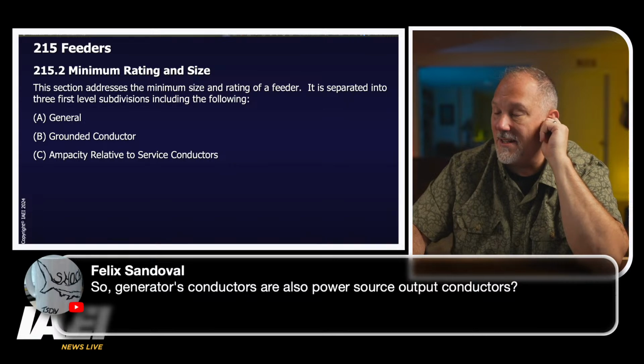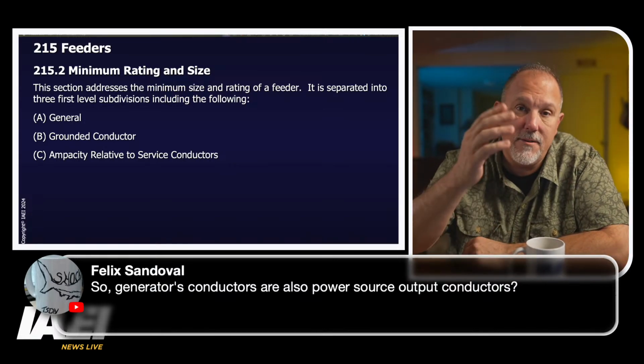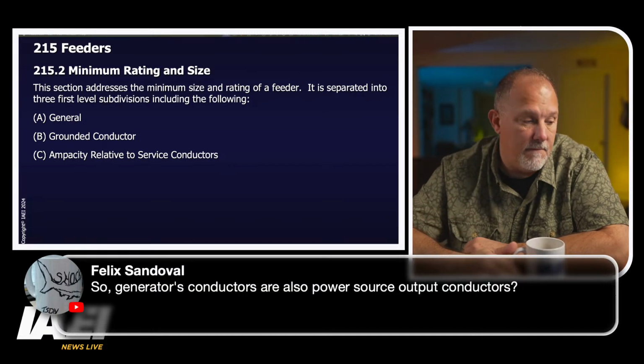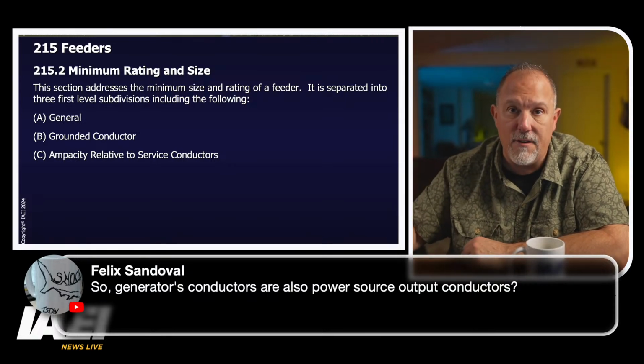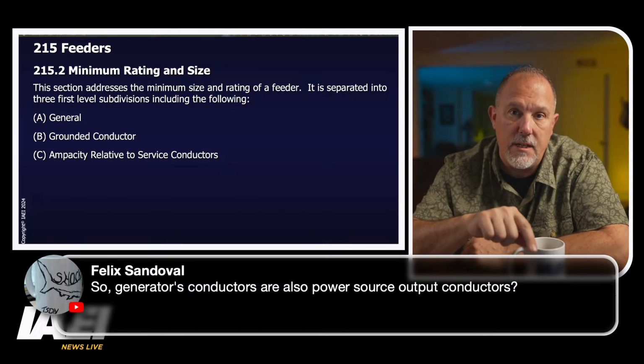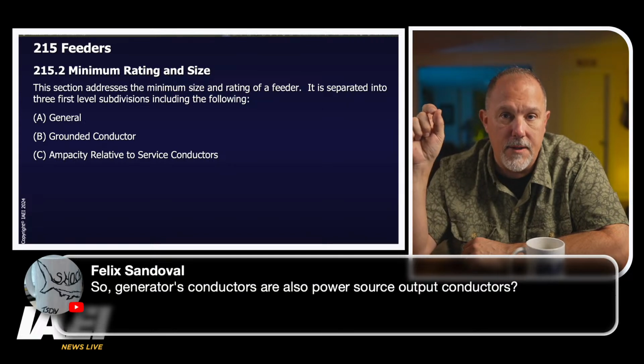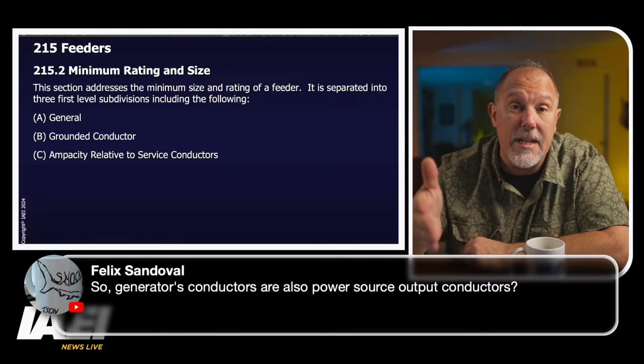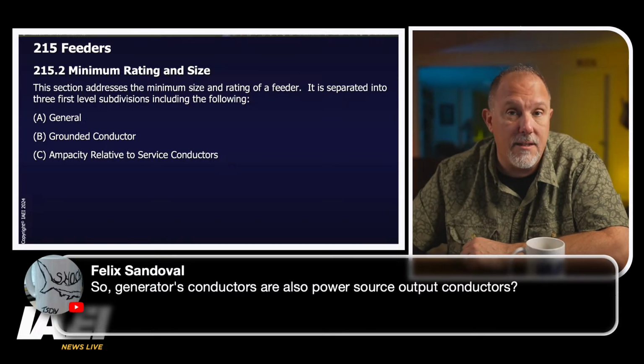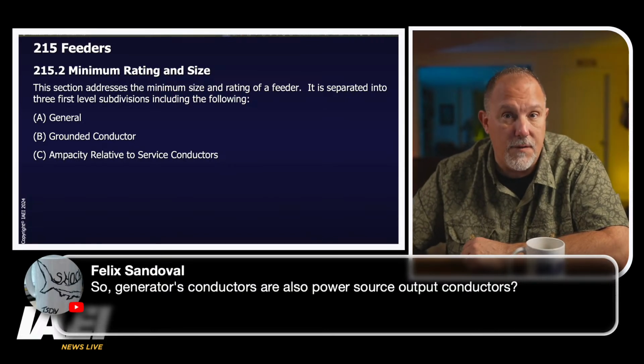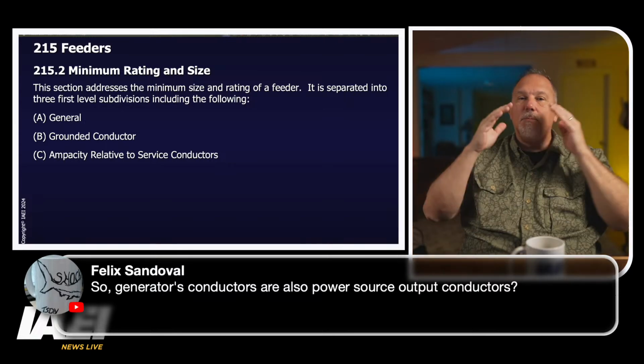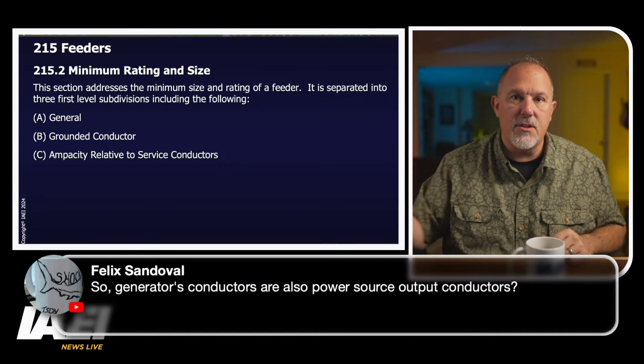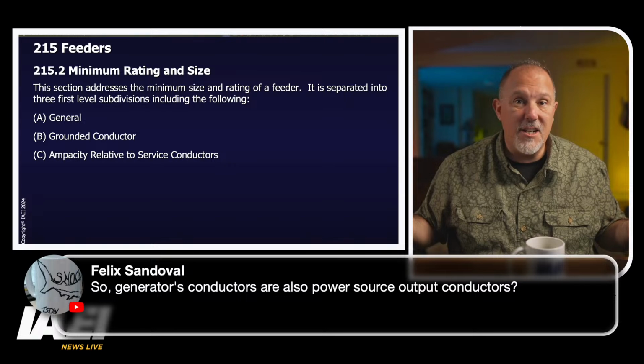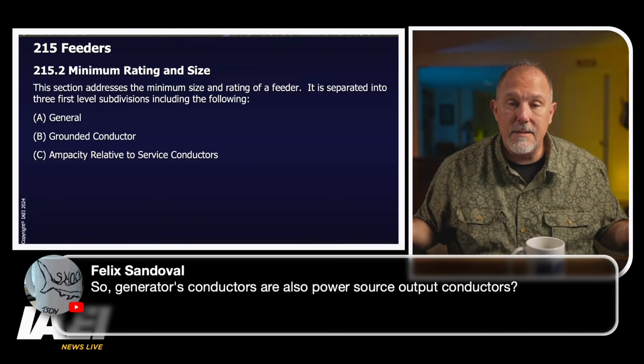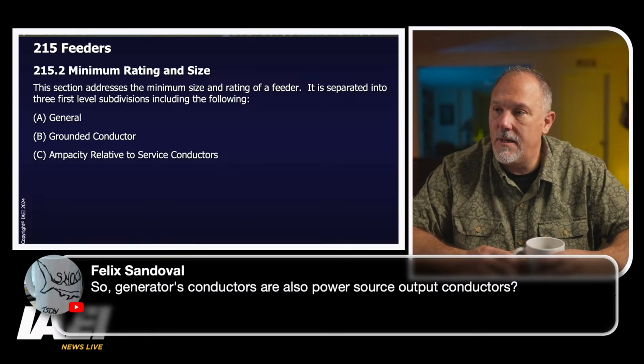Generator conductors are also power source output conductors. Well, Felix, they meet the definition of it. A generator is a power source. I don't agree with it. It meets the defined terms, but we treat them like feeders. They are feeders. You wouldn't go anywhere other than 215 to understand what to do with the generator conductors that are powering the system, because they are feeders. Panel 13 understands the definition of a feeder. Panel 13 understands Article 215. Apparently, we have some challenges over in Panel 4. And the principal reason is because in a PV system, they're a source, and the generator is a source too. Anyway, they are feeders.